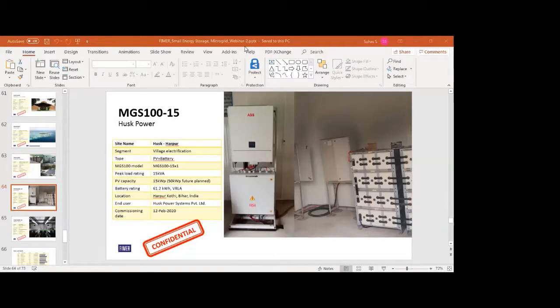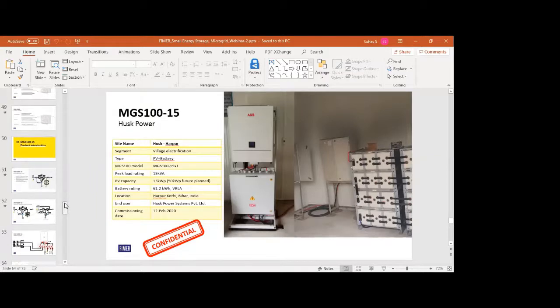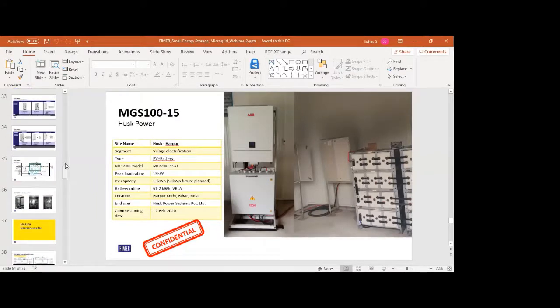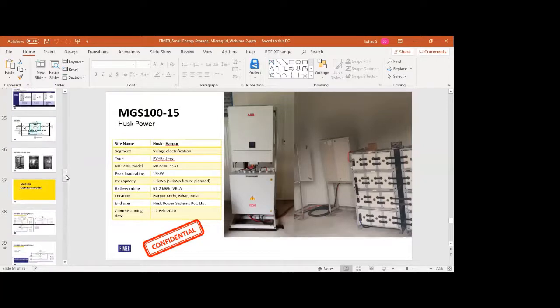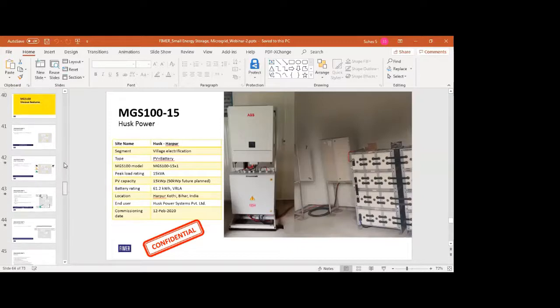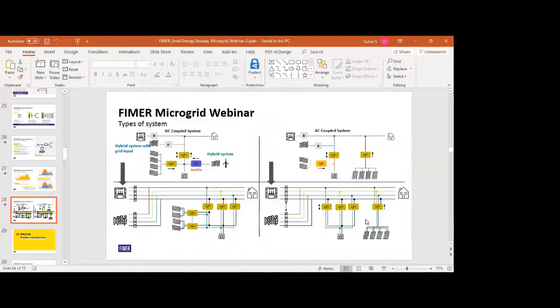What are the advantages of a DC coupled system? Sir, DC coupled is very advantageous when your intention is to store the majority of your energy. For example, if there is a load in an off-grid village, where solar usually generates during daytime when the loads are less and the generation is more, and you want to store that energy in your battery so that you can use it in the evening time. Because of the DC coupled nature, let me go back to the slide, the efficiency of charging the battery is best. So this will lead to better energy drawn out of the batteries. It will give some economy also, because you need not install more batteries or more PV in order to achieve the same thing.